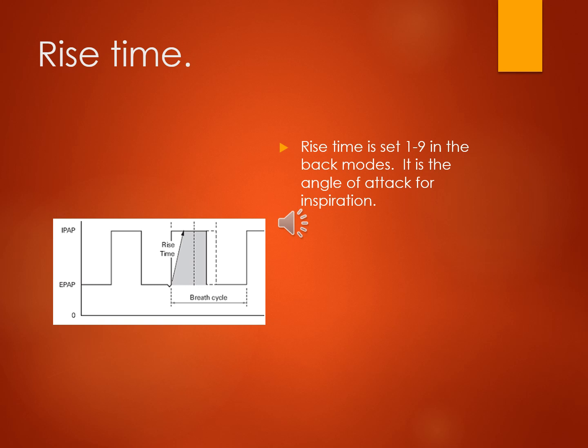It's going too slow to meet the volume demand. So whenever we make a change on a ventilator, or set up a ventilator, we should be looking at those numbers ahead of time to see where they are, and if we're adjusting them, we're looking at the volumes to see what they are. If I had a patient that was doing really well at an outlying facility, and I'm looking at the rise time, if I can mimic that, that would be great. And if I didn't know what that numeric value was, or didn't understand their ventilator, I can adjust my rise time to get a similar volume. So just be very careful with what you're doing and make sure you know what you're doing before you just start spinning dials.